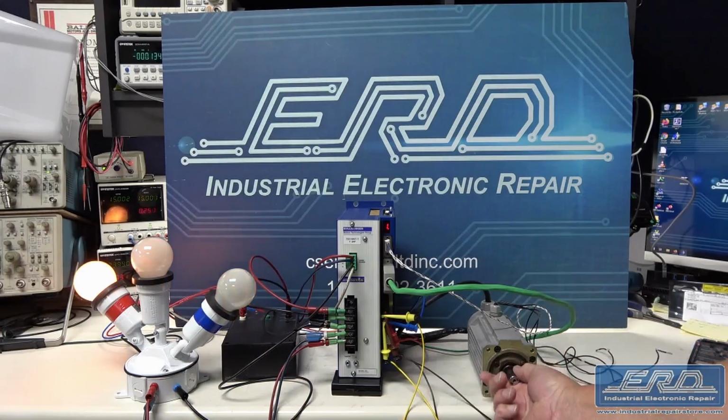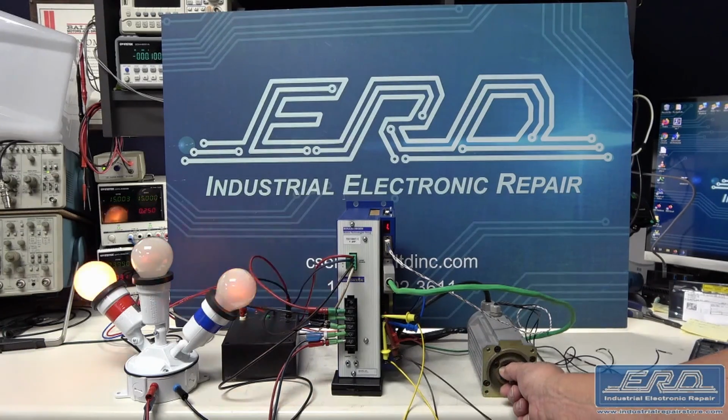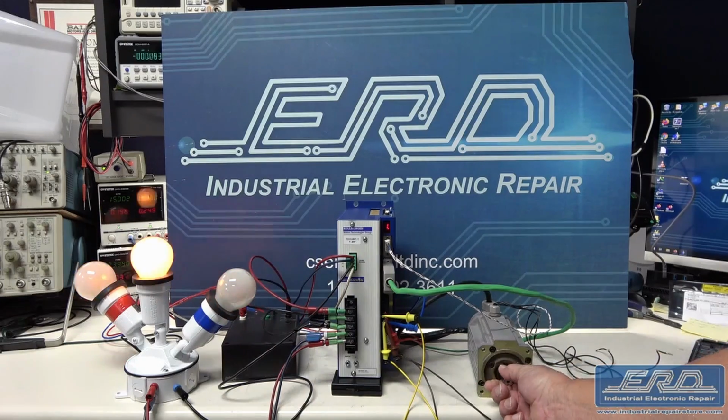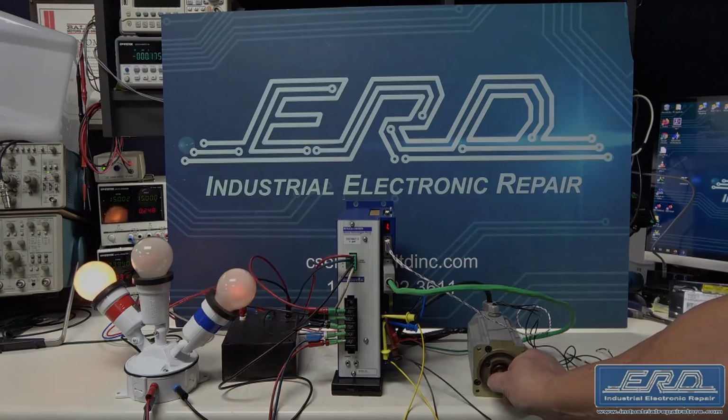ERD has hundreds of motors, but we cannot have every custom motor required for every job, which is why we use the linear light load to simulate the windings of a motor as shown in the test video. This form of test covers 99% of what a motor would show as long as we commutate the outputs with one of our many motor feedbacks.